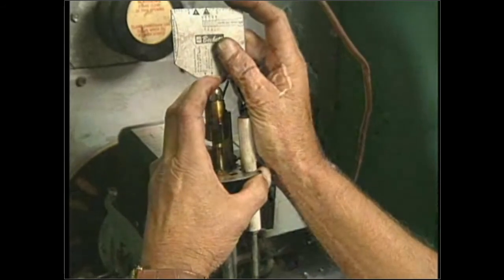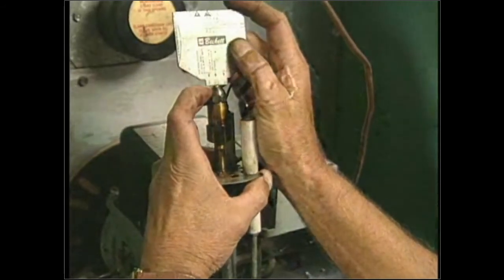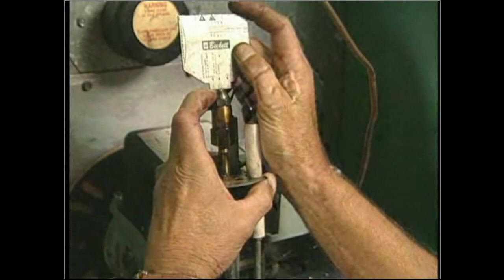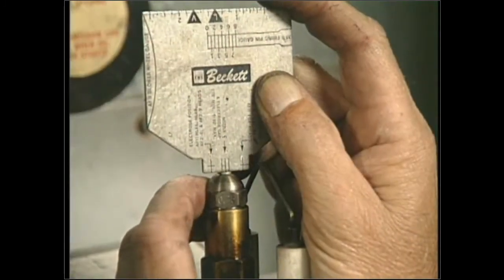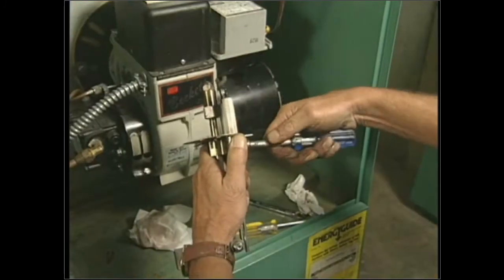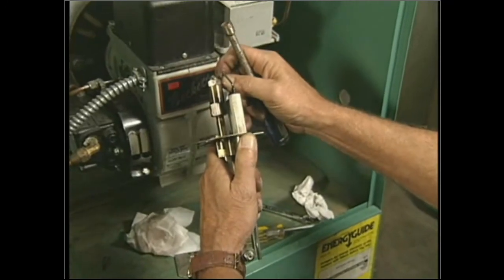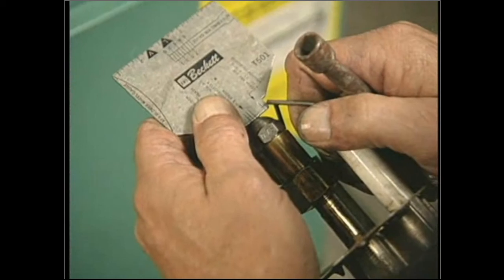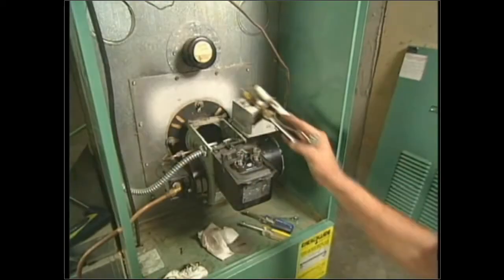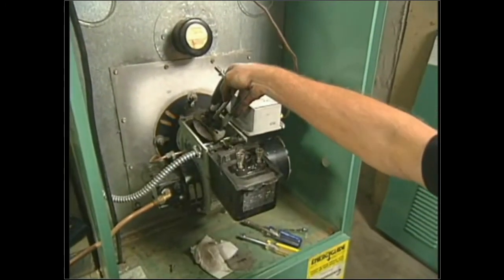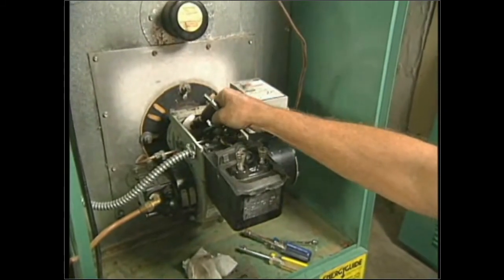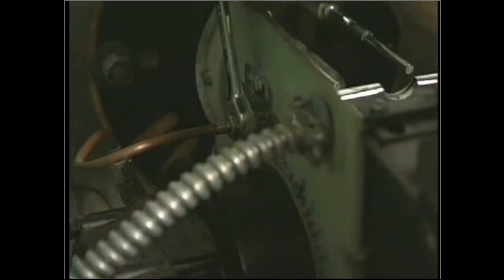Additional procedures for burner assembly include the measuring of the electrodes in relation to the oil nozzle. And for more experienced technicians, adjustments can be made by loosening the electrodes and resetting them with the proper measuring device. Upon completing the inspection and documenting the nozzle sizing and spray pattern, the burner should be reinstalled along with the transformer cover, and all the mounting screws should be re-secured.